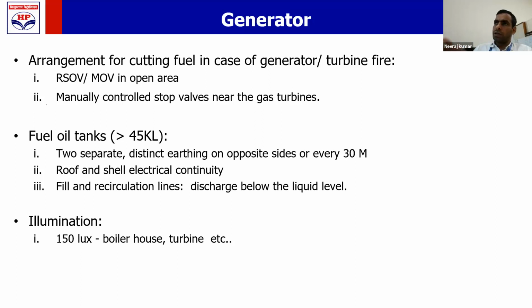Roof and shell of the tank shall be made electrically continuous. If it is a fixed roof tank, no issue, continuity is already there. If your fuel oil tank is a floating roof tank, then you are supposed to provide bypass conductors and internal shunts. Shunts which are inside, not outside. Earlier tanks had external shunts. So roof and shell continuity will be maintained.